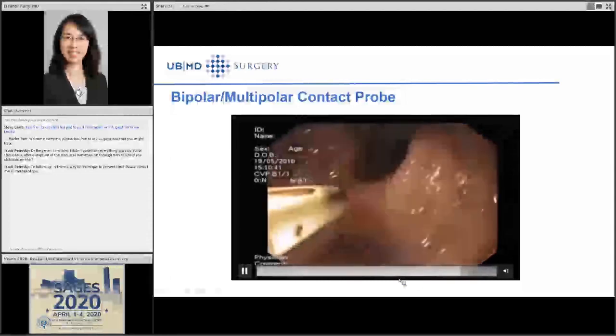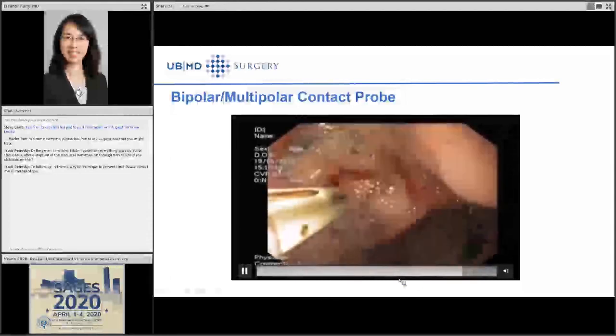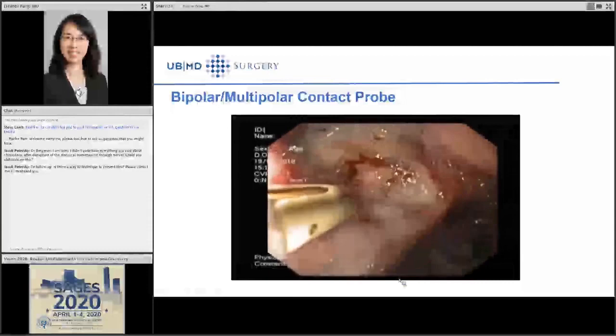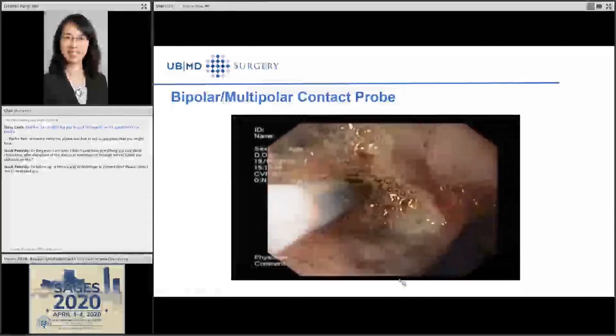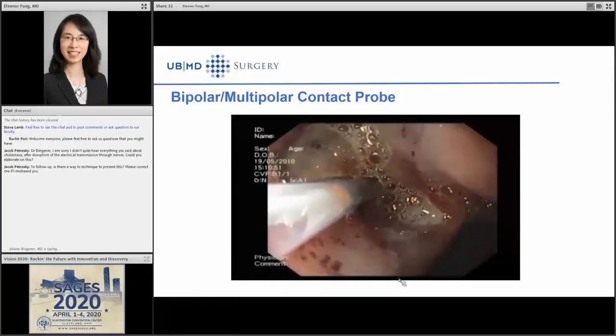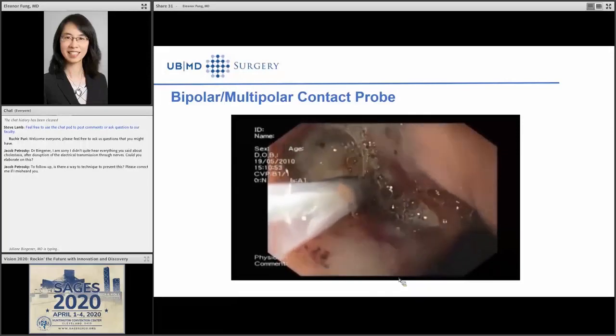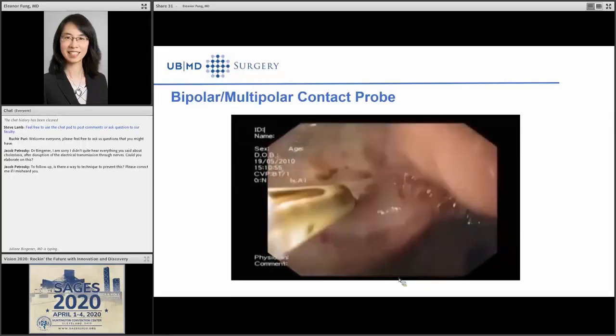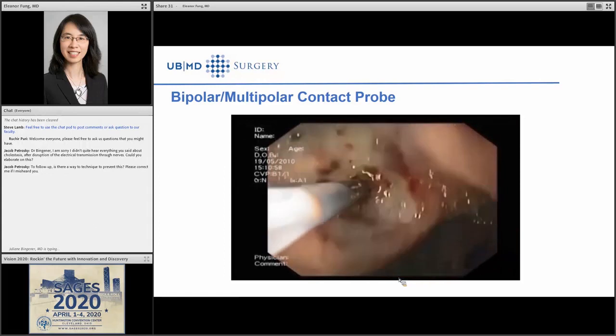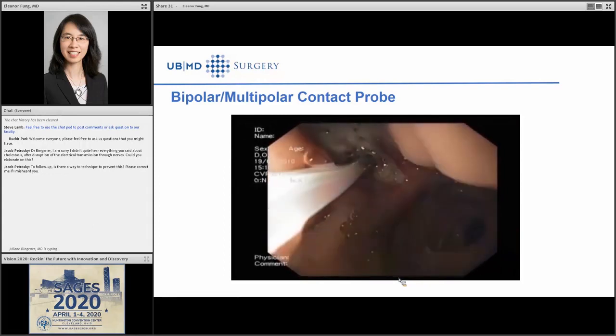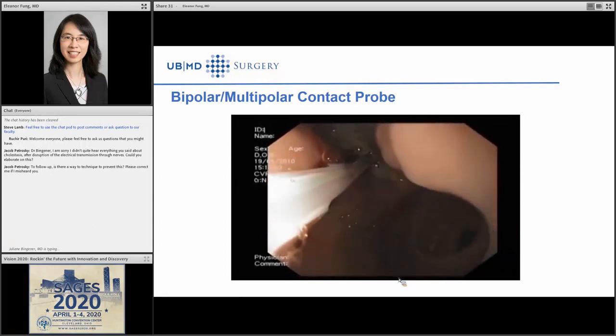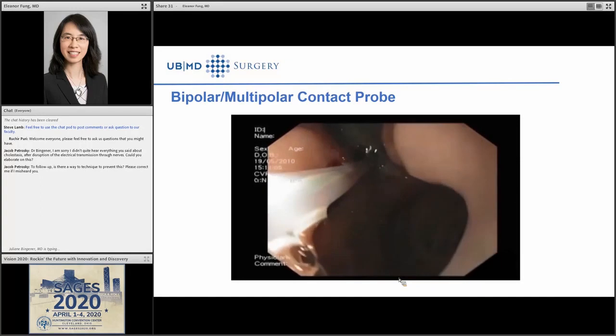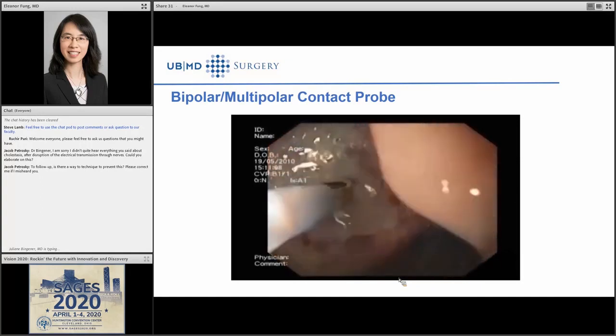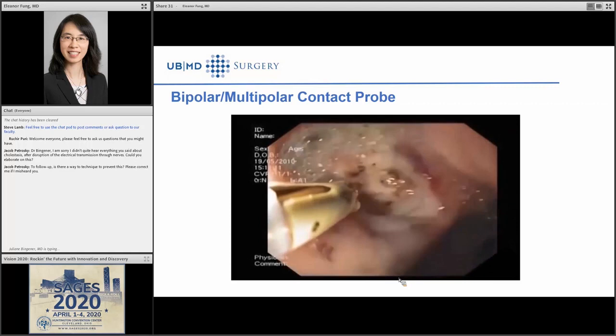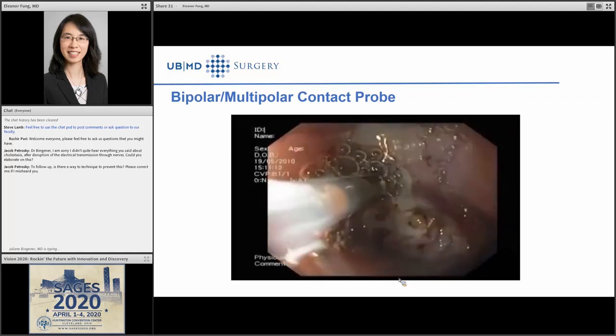So here's the bipolar probe, and this is a contact thermal device, as I mentioned. You want to be applying the probe directly on the tissue and apply mild to moderate pressure onto the area you want to apply thermal energy, with 4 to 6 pulses. This one in particular has an irrigation port at the end, which can help visualize exactly where you're coagulating.